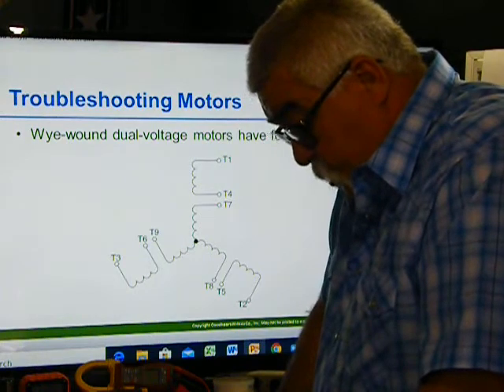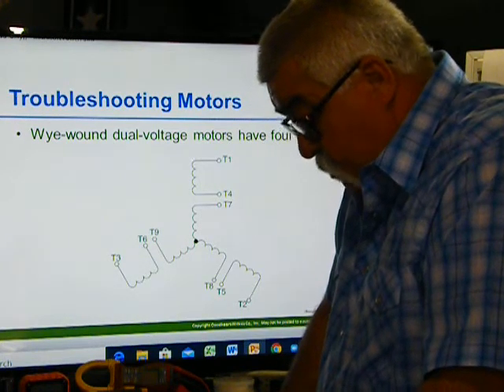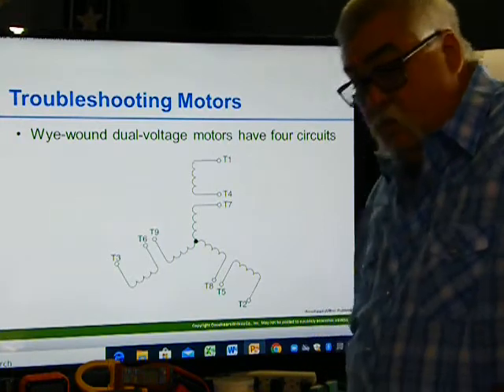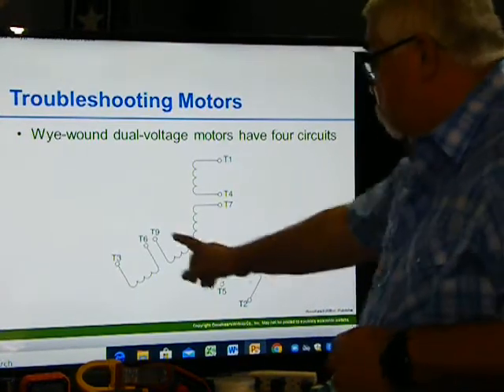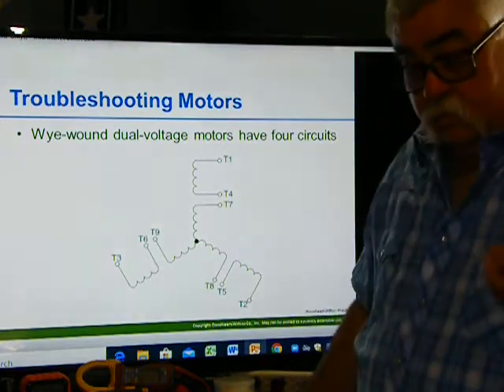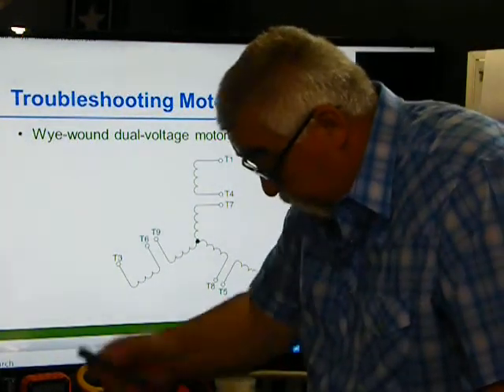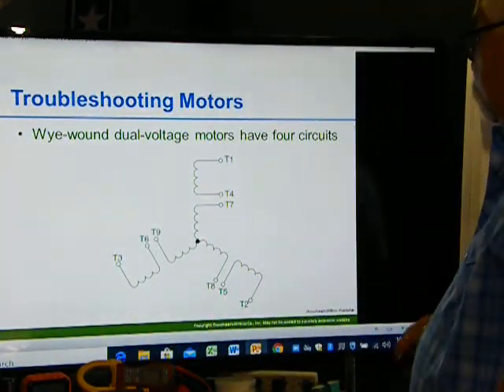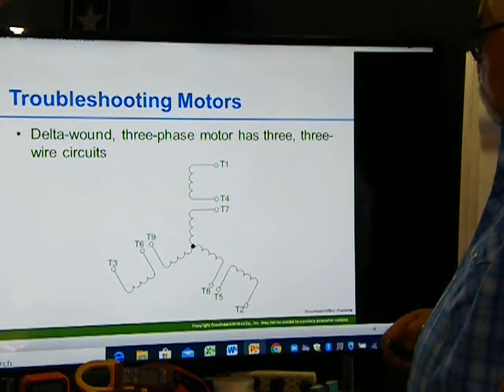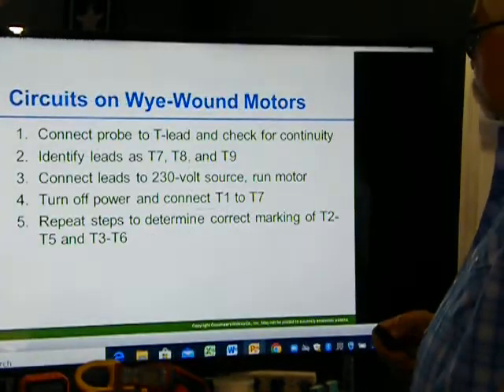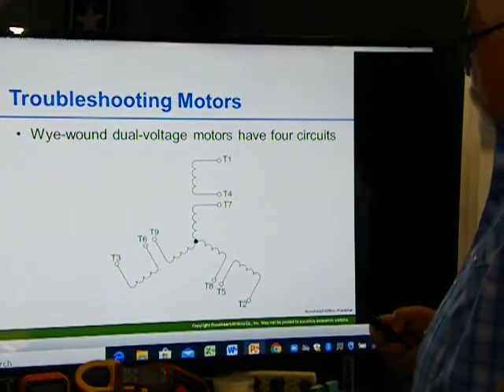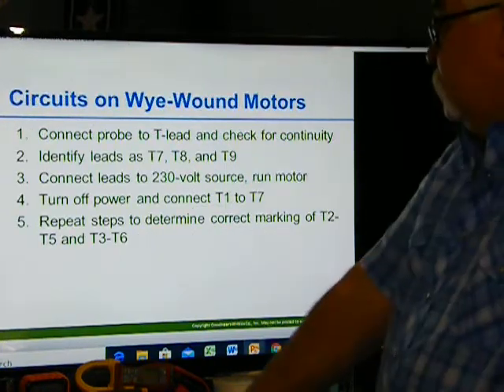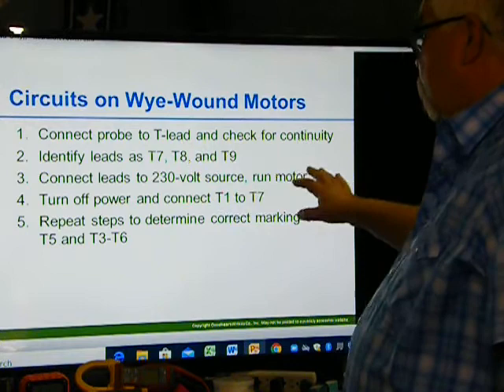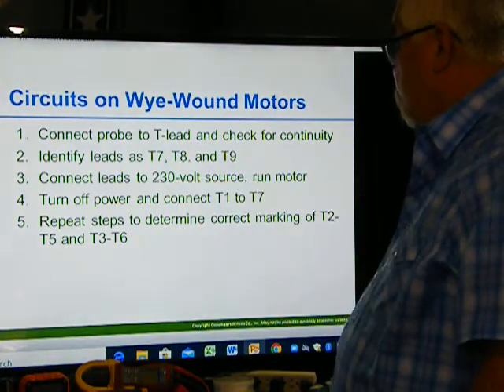It says use a continuity tester or ohm meter, connect one probe to any of the T leads. When it's talking about the T leads, the motor usually has 9 leads. So T1, T2, T3, all the way up to T9. And with a delta, it's the same thing. The circuits on the wye say connect the probe to a T lead, check for continuity, identify leads T7, T8, T9.